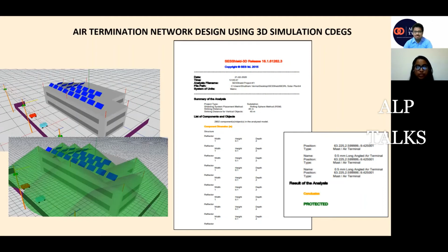Coming towards the lightning protection system, it also plays a very important role, as I have already told you. In this also, the validation is very important, because we are doing the designing, but we cannot say that at these points only the lightning will hit. At the points where I am putting the air terminals in my design, I should validate that if I have shown that you have to install the terminal at this point, it is protecting your building.